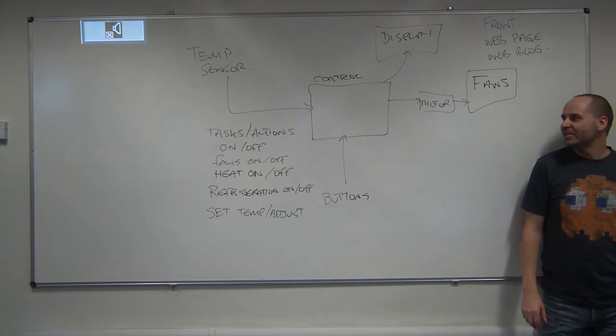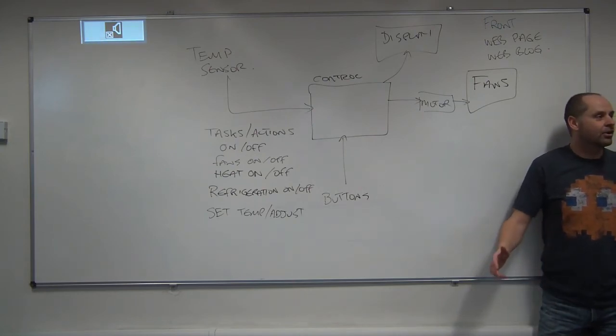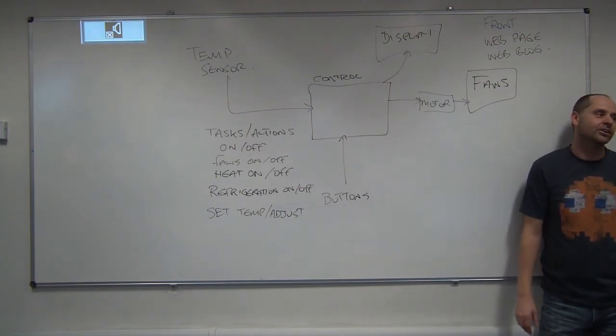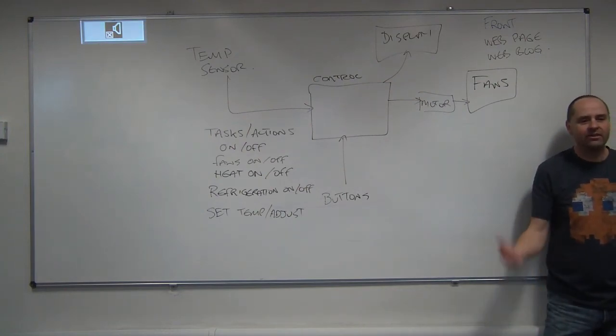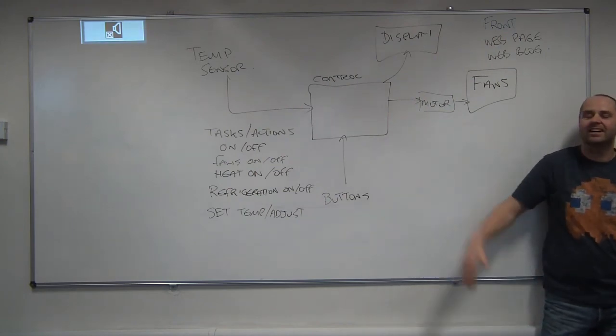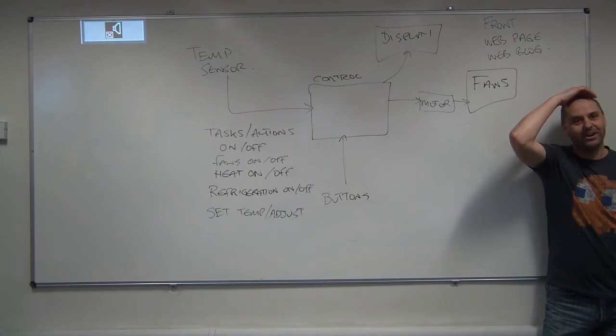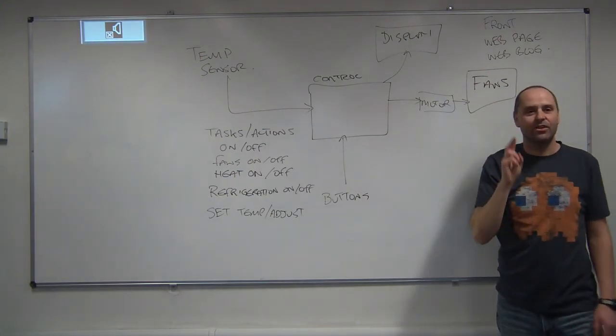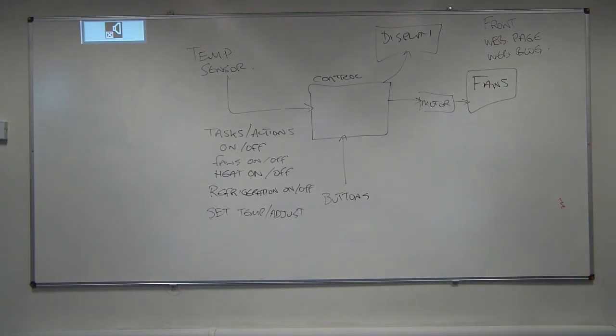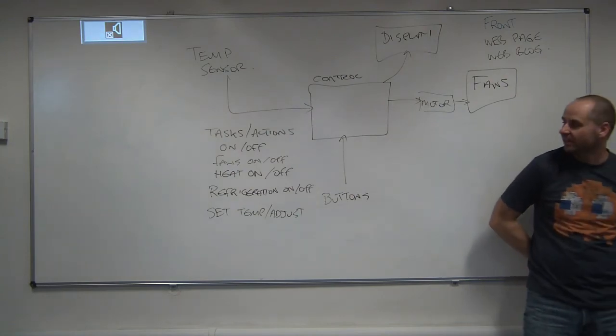Everything died. Everything died because the control system went, right, okay, we need to put more acid in the water. The sensor kept saying, there is not enough acid in the water. So it emptied the entire acid tank. And it destroyed all the data for the whole year, which was quite amusing. And they didn't think of doing one simple thing. What could they have done to try and stop that happening, do you think?